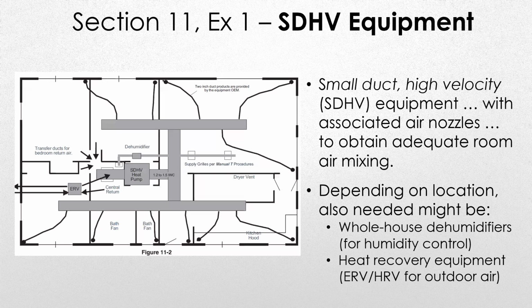So the first example we have is a small duct high velocity equipment. Probably a lot of you are used to seeing it. This one was based on possibly installation in Homestead, Florida, or someplace in a highly humid area. It uses nozzles, as they always have, to obtain adequate room air mixing. And of course, if you put in small duct high velocity equipment, you want to install it according to manufacturer's installation instructions.